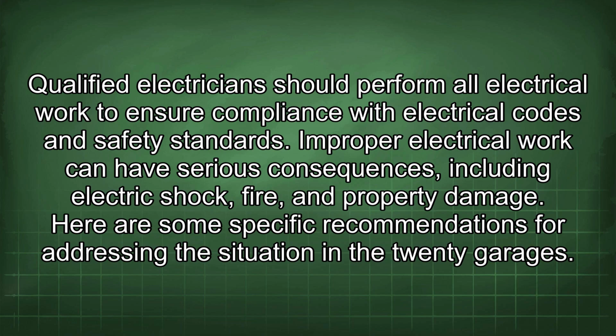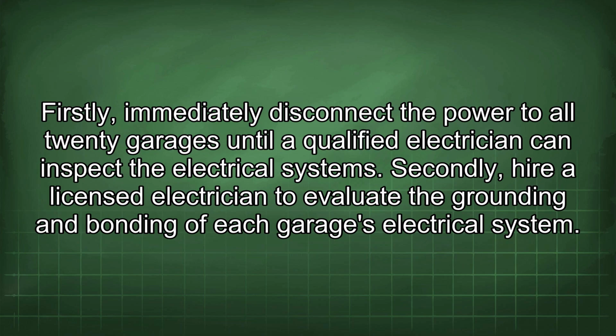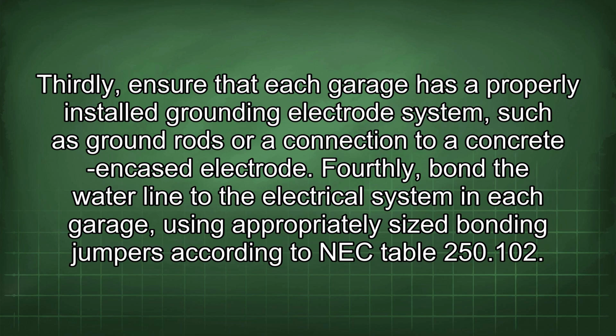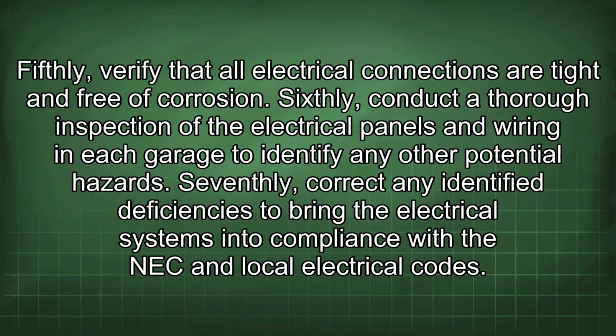Here are some specific recommendations for addressing the situation in the 20 garages. Firstly, immediately disconnect the power to all 20 garages until a qualified electrician can inspect the electrical systems. Secondly, hire a licensed electrician to evaluate the grounding and bonding of each garage's electrical system. Thirdly, ensure that each garage has a properly installed grounding electrode system, such as ground rods or a connection to a concrete encased electrode. Fourthly, bond the water line to the electrical system in each garage, using appropriately sized bonding jumpers according to NEC Table 250.102. Fifthly, verify that all electrical connections are tight and free of corrosion.